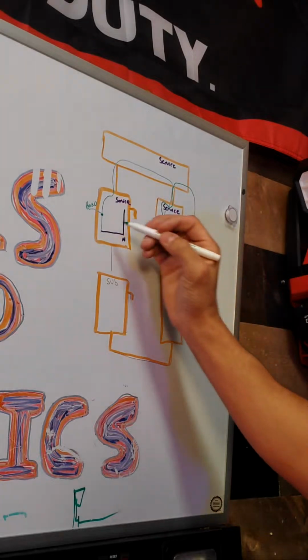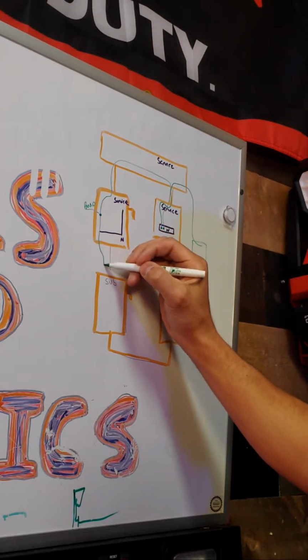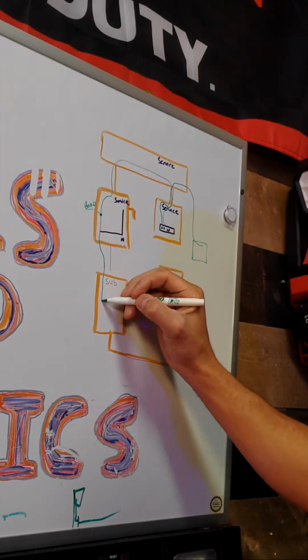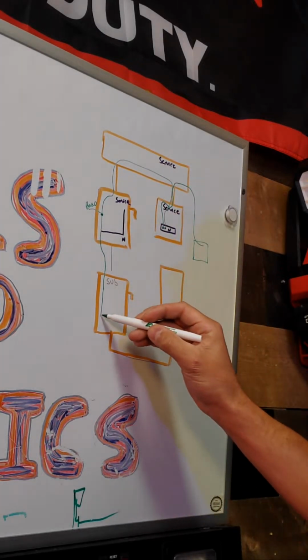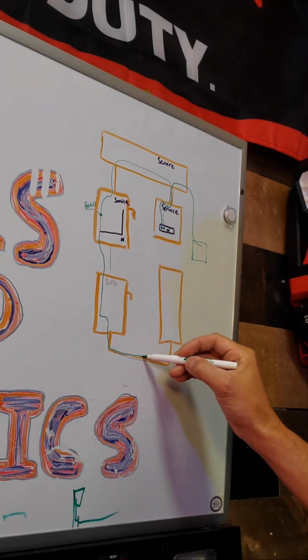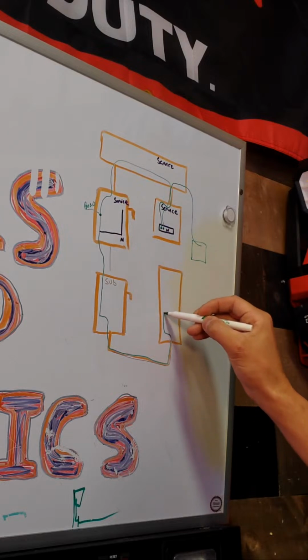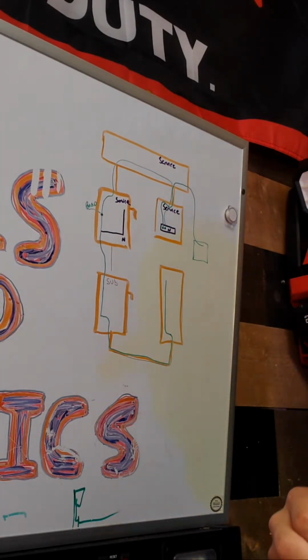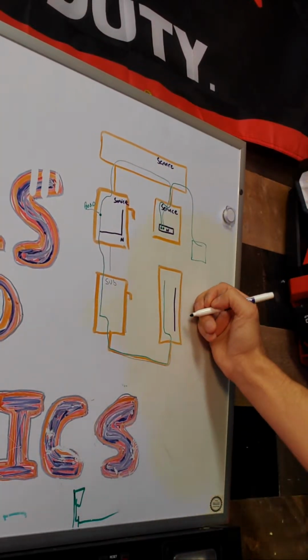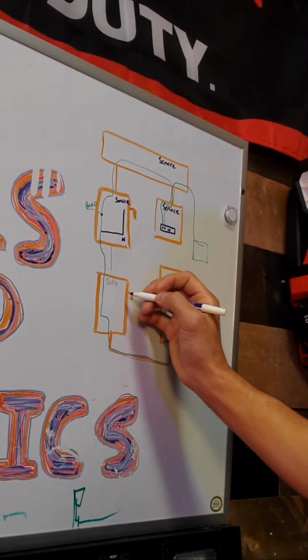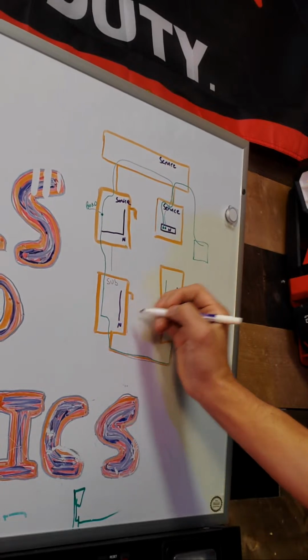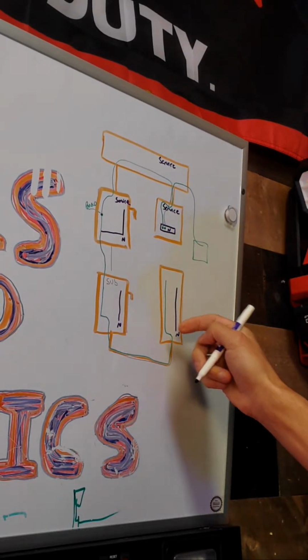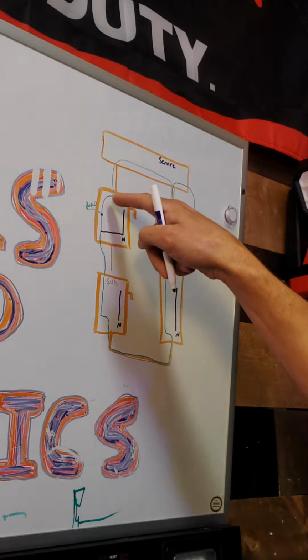And then from there, that ground and the neutral went to the sub panel separate. And if we follow the ground path, it also went to the sub panel that was inside. And we got a neutral there, and we got a neutral bar there that's isolated. Those were isolated—this was bonded together here.